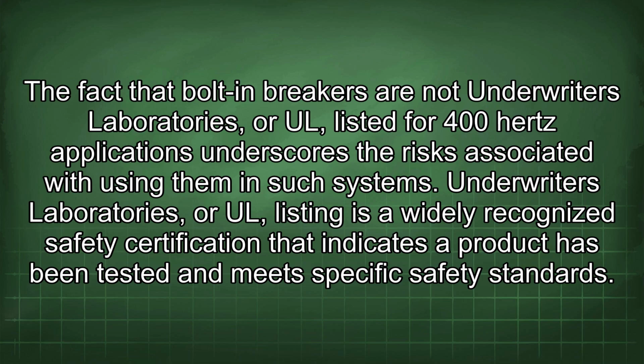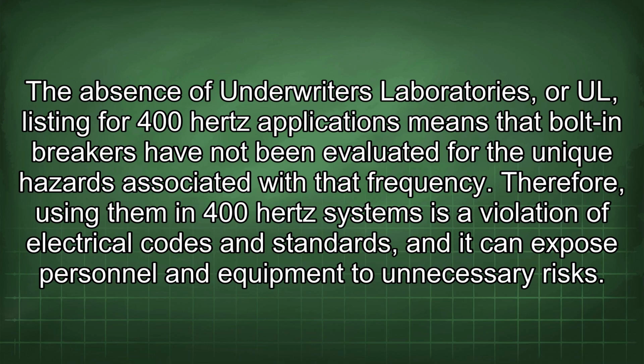Underwriters' Laboratories, or UL, listing is a widely recognized safety certification that indicates a product has been tested and meets specific safety standards. The absence of UL listing for 400 Hz applications means that bolt-in breakers have not been evaluated for the unique hazard associated with that frequency.